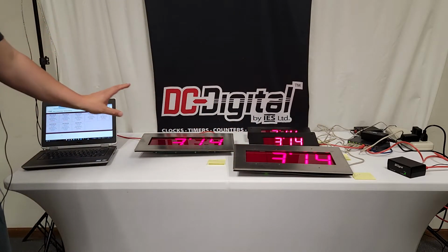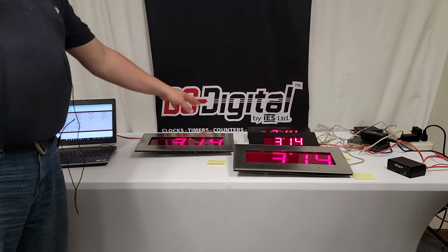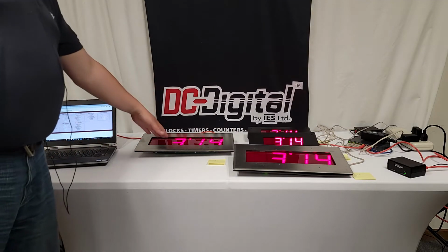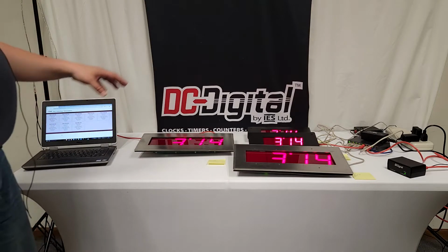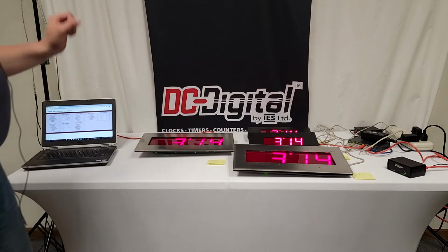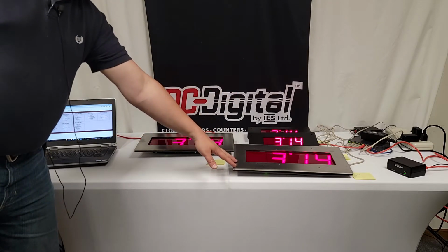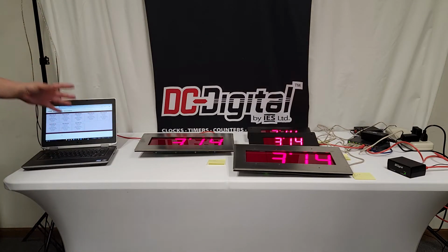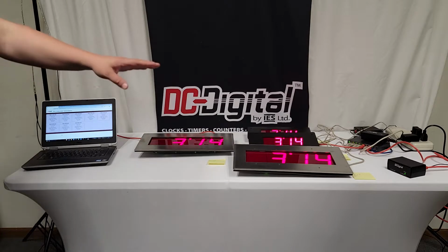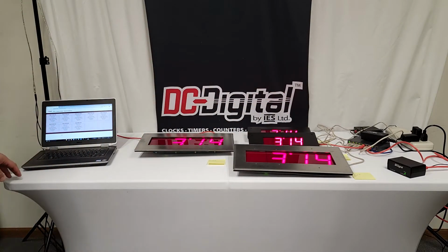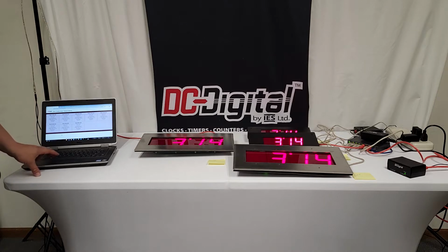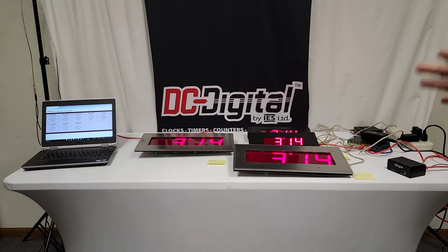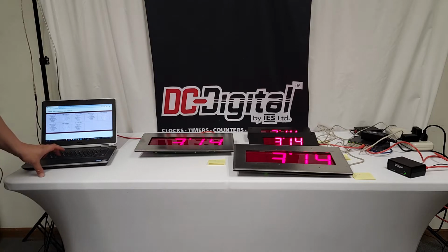Normally, to access and change any configuration on any one clock, you would have to know the IP of that clock, go to that IP address, make your changes, and then type in the IP address for the next clock, go to that clock and make your changes. What we've done here is bring all those clocks together into this box, which saves their IP addresses for you and saves you from having to go to each individual clock to see what the status is, where they're at in gathering the time. This is when it first starts up and has no IP addresses registered.